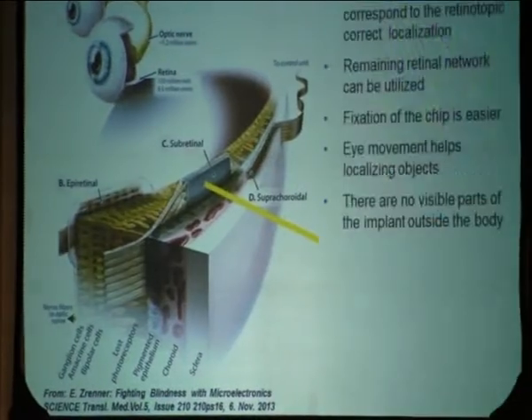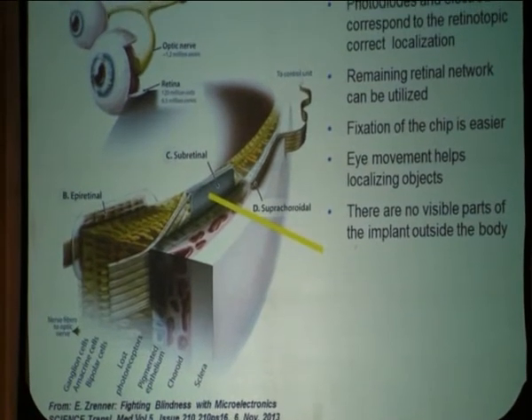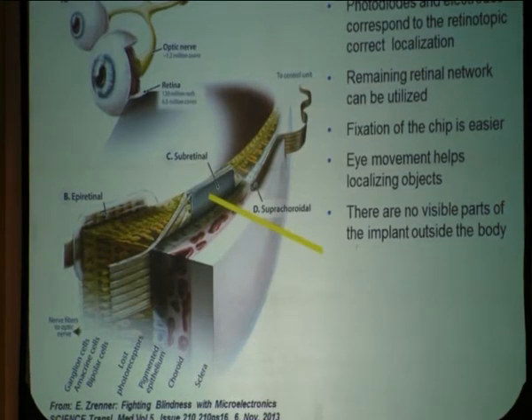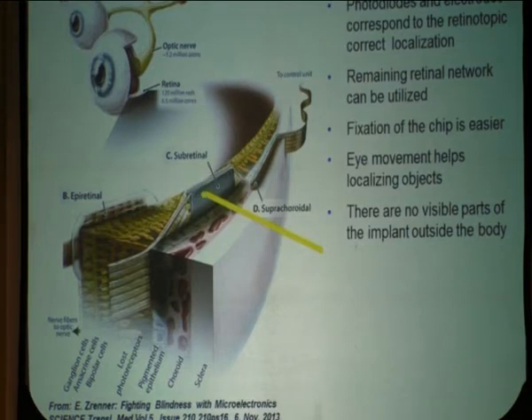Here you see the chip when it's implanted, and it has some advantages. The photodiodes correspond to the retinotopic correct localization, so there is no learning process. You use the remaining retinal network. The fixation of the chip is very easy, and the eye movements can be used. This is in contrast to the epiretinal project. So you have no visible parts of the implant outside the body, and you can use this implantation in retinal degenerations, not in other types of blindness.